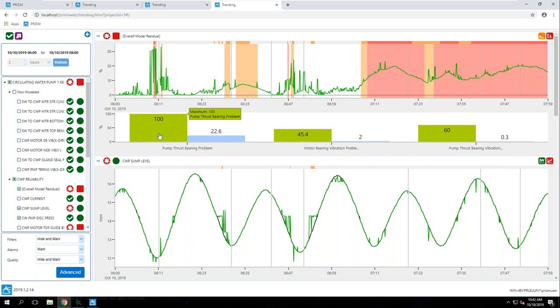There are two different bars on this bar chart. The first is green, that's an instantaneous pattern match. Blue is an average pattern match. So at some point in time on this overall model residual chart, we had a 100% instantaneous pattern match, but over the entire span, over this entire 2 hours, 22.6% of the time we had a pattern match against this failure mode.